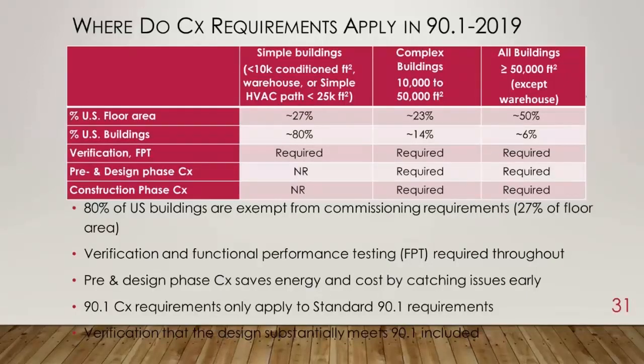One other thing I didn't mention is that, at least in the mechanical section and increasingly in the lighting section, the controls are becoming more important as far as where we expect the energy savings to come from. Unfortunately, most building officials, with a few exceptions, are not really in depth with the controls. We felt it was very important that for the more complex buildings we have a commissioning agent, typically going in and doing trend logs and looking at the controls, and coming back and giving the building official assurance that the controls in this building are actually implemented. We've added language in 90.1 that not only shall the controls be capable of doing what they're supposed to do, but they are supposed to be configured to do those set points and requirements at the time of inspection, so before the occupancy permit, the actual controls should be set up and in place.